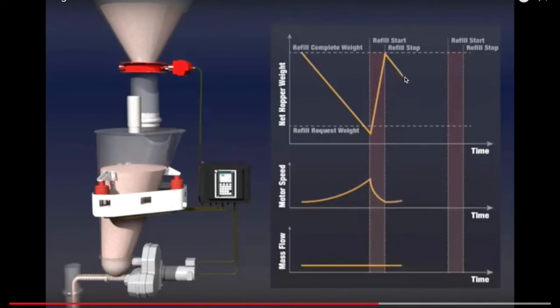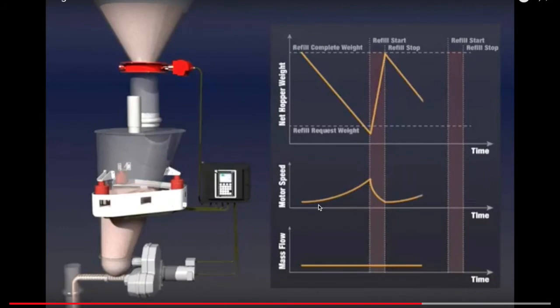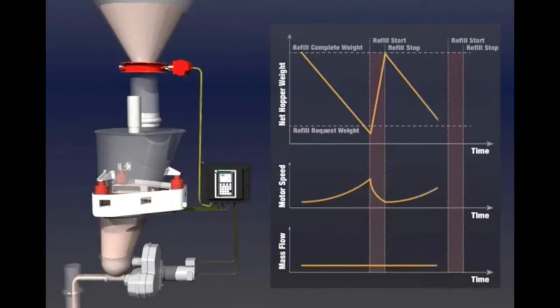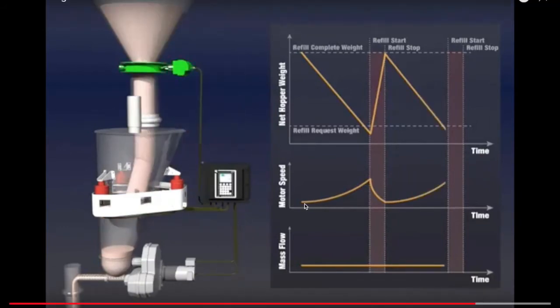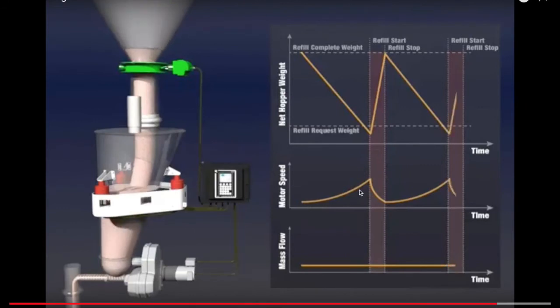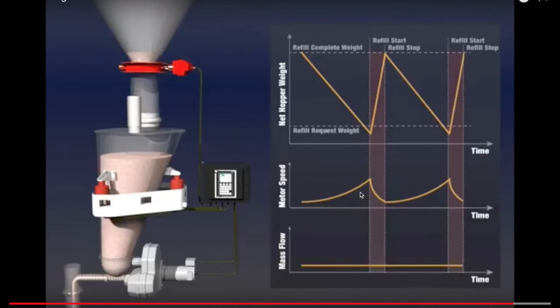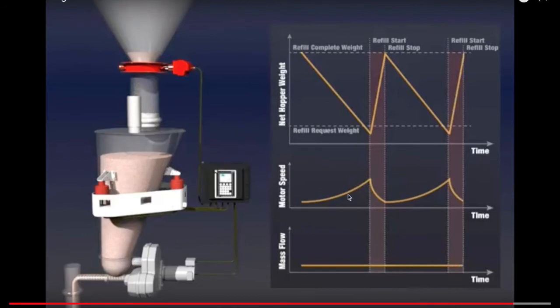The motor speed, which is depicting how fast the screws are turning, starts out at a lower rate and has to increase as there is some head pressure caused by the powder. Powder will intrinsically act a little bit like a fluid, so that the more powder that is in the surge tank, the slower the screws have to turn, because there is some amount of pressure pushing the powder through the screws.